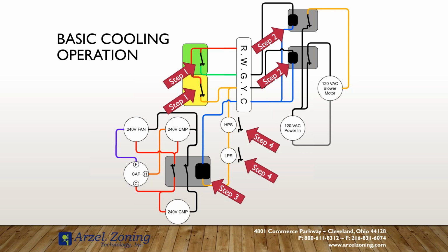So if we have everything operating inside, our blower kicks on right away, it kicks on at high speed. We know that the furnace is working. We know that the thermostat's working. We move to the outdoor unit. We're missing our voltage there. We have to back up because there's a break in that line somewhere. Now it might be a high pressure switch, might be a low pressure switch, might be a mouse, a weed whacker, a dog, a cat, some kind of animal chewing on the lines. We have to back up and take a look at that. But if it's there, then our compressor and our fan will start, as long as we got the high voltage present as well.